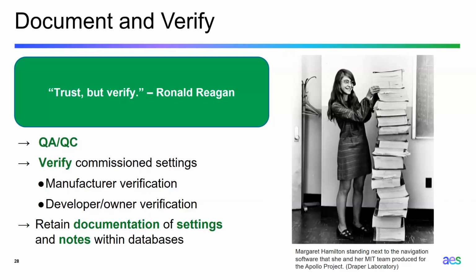Then retain your documentation. When you have an inverter that needs to be replaced, what do you do if you don't have those settings saved? How do you make sure that if the manufacturer is doing repairs and putting another inverter there, they put the right things on? It's very hard if you haven't saved that documentation, and it takes field resources you don't want to spend. If you just save the documents and notes, you have something to reference. That's very important to this process.